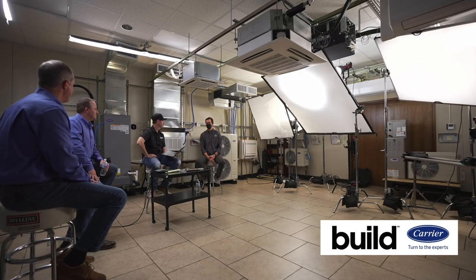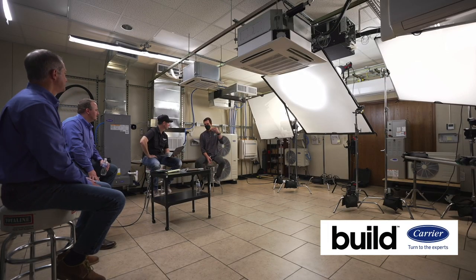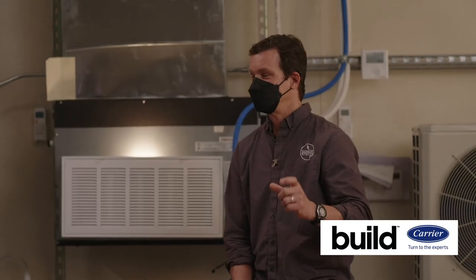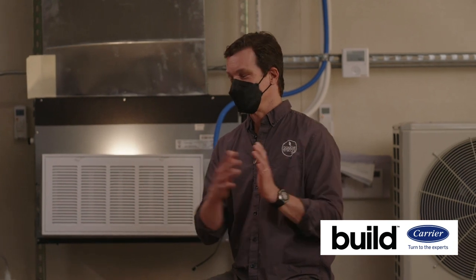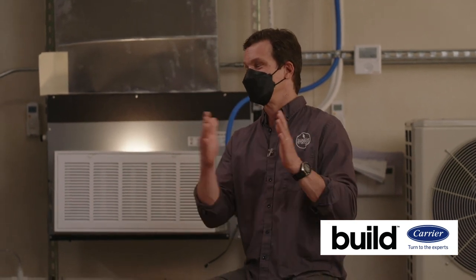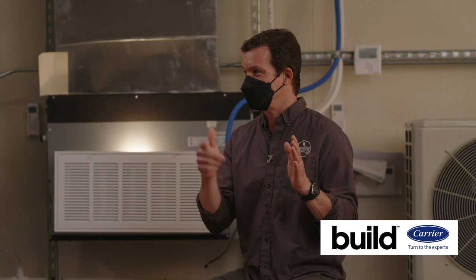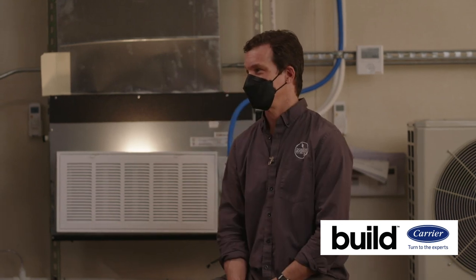Dehumidifiers are supplemental, but his question was, does the increased runtime of VRF dehumidify better than conventional equipment? There's only a certain amount of heat that needs to get removed from that room, so whether you remove it fast or slow, if you remove it fast, it's a very cold coil for a very short time, probably generating more condensate. The point is, you've got to get supplemental.